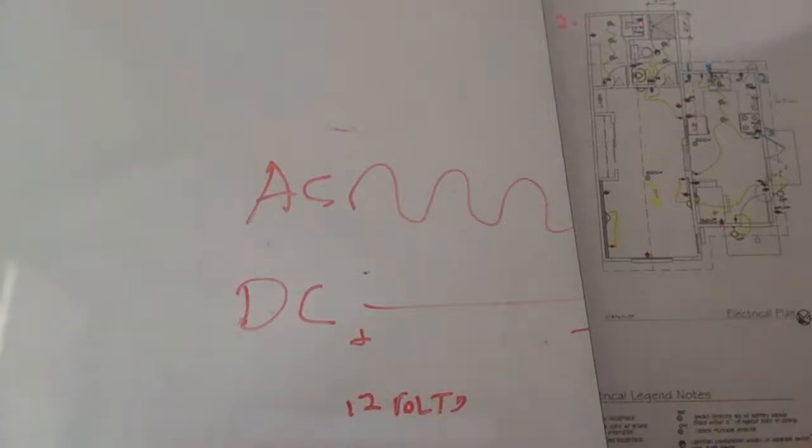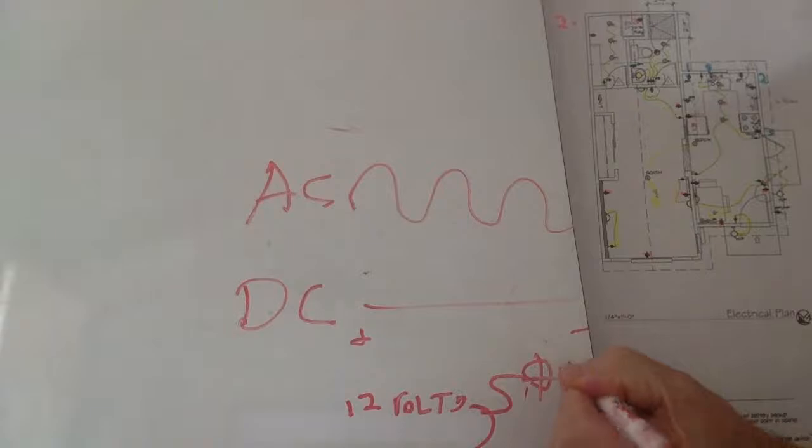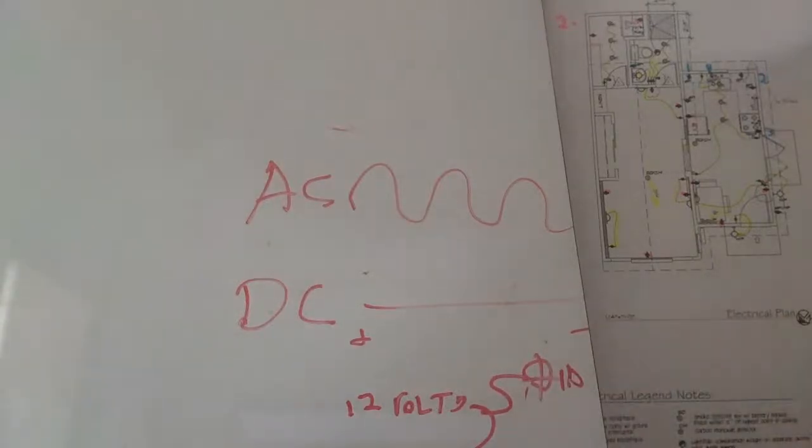At the transformer, you can have 12 volts. After 100 feet, you're going to lose a volt. You'll get 11 at your light down here. So you'll put your meter on here. This will say 11. It might even say 10. At 9, the light will not light up. Say you are 300 feet away.